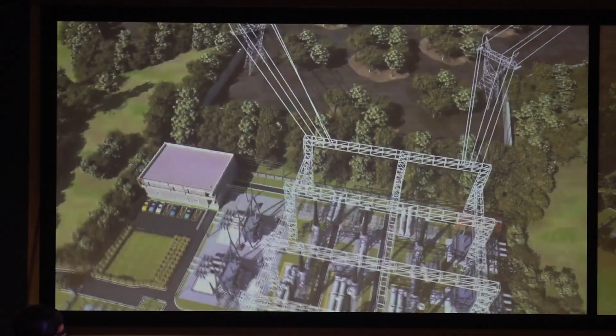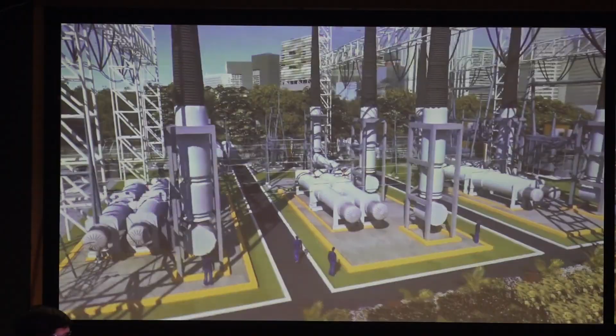At GIFT, the power reliability is 99.999%, implying an annual outage of only 5.3 minutes. It will have a feed of 750 megawatts from two 400 kV lines. The receiving substation will be a gas-insulated switchgear substation.